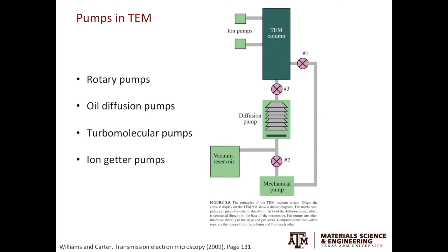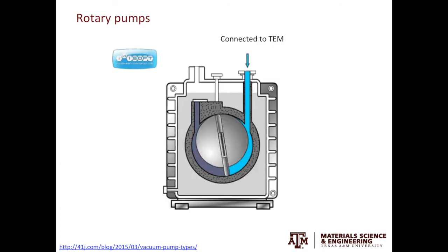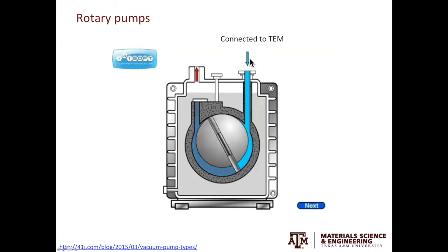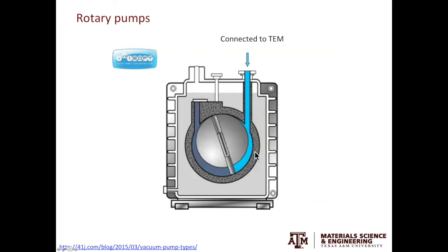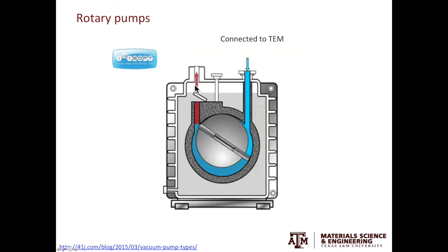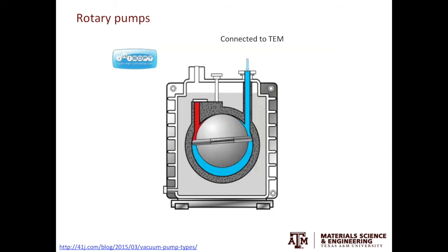Starting with the rotary pumps. As the name suggests, the rotary pump has a rotor. From this animation, we can see the TEM is connected to here. As the rotary arm spins around, the air is pushed from one end to another and expelled to the atmosphere. In this way, we can get a better vacuum from the TEM end.